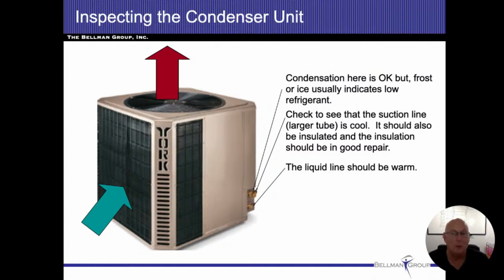Now, I'll put my hand over the top of this coil and make sure I got warm air coming out of it. But again, that's just a rule of thumb, all right? So that air coming out of there should be probably somewhere around 15 degrees over the ambient air temperature. So whatever it is, it's going to feel warm to my touch, all right? On the suction line, because we said the suction line is cold, and it's going to be warm or hot and humid outside, so condensation will form on that.